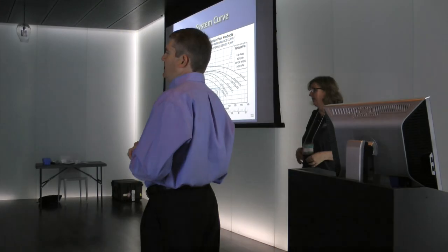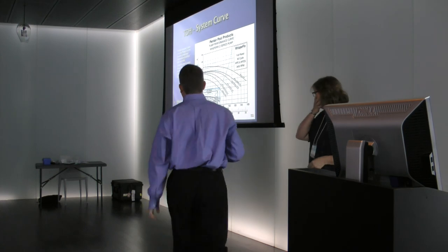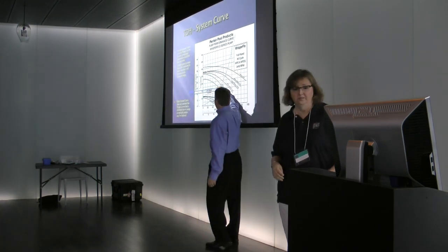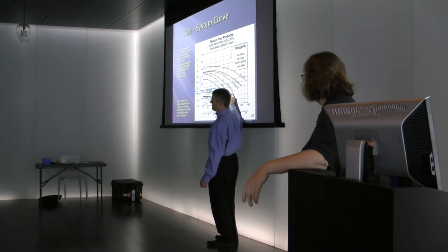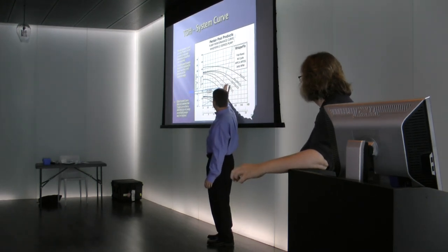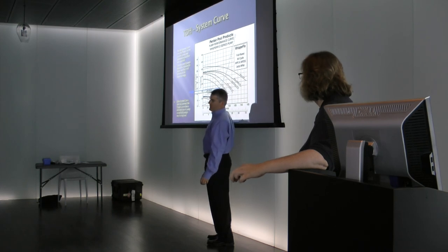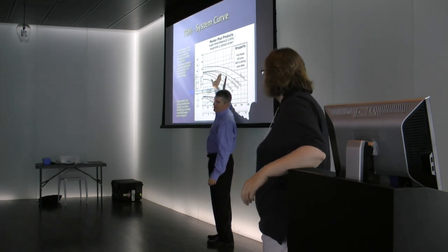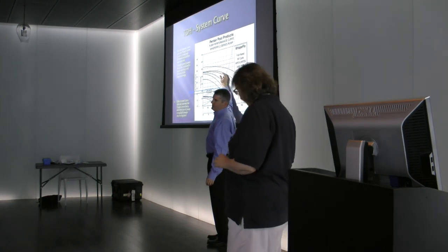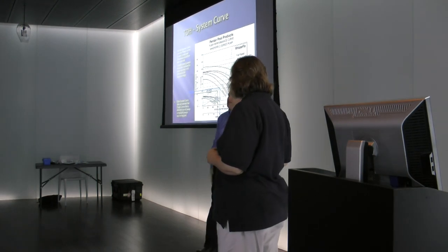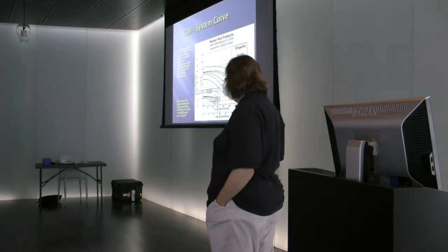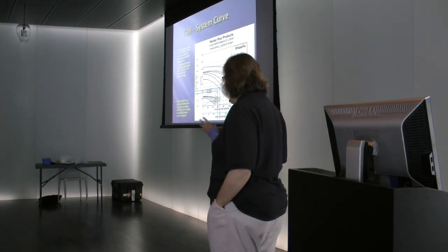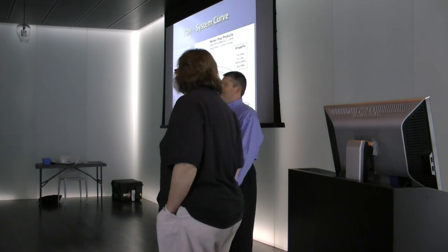Yeah. And that's why, what happens with the valve is that you're operating at the wrong spot, and you may be operating off the end of the curve, and you're throttling the valve to bring your system curve in line with the sweet spot of the pump. And what I would rather do is just slow the pump down until you are at that spot. Now it's tricky to try to explain this in such a short time. I do this in a 2-day class where you'll really get it. But I think you explained it just right.